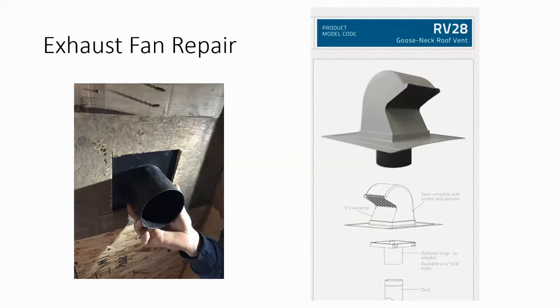The connection between the adapter and the vent is above the roof deck. So if you do get any leakage at that point, it's already outside and above that shingle line, so it's going down. Obviously, it gives us something to tape a pipe to, which is what we need. Your common silver metal gooseneck that sits over top of a hole, there's nothing there to adapt to.